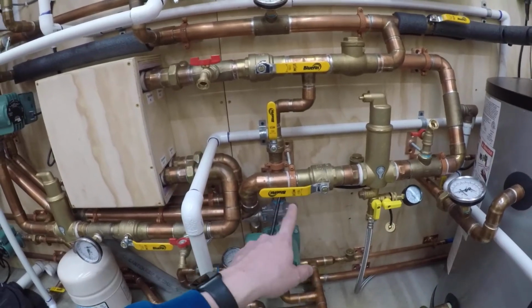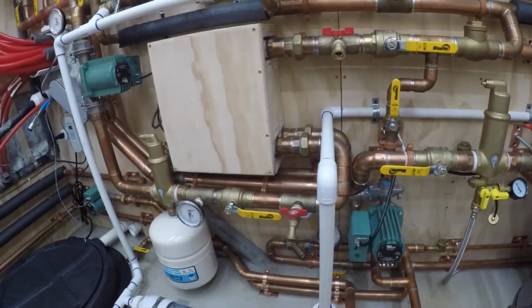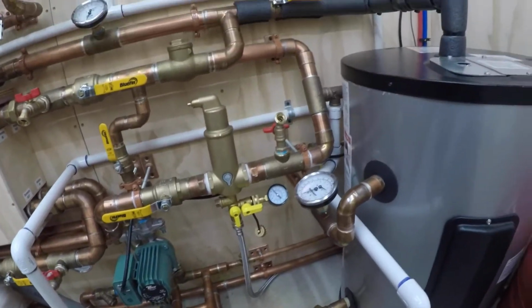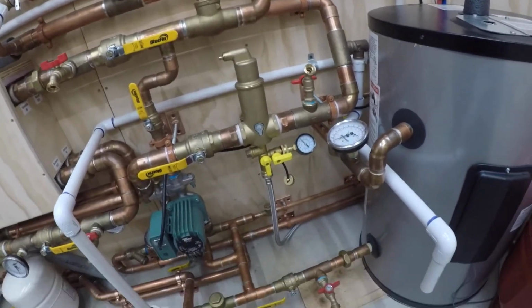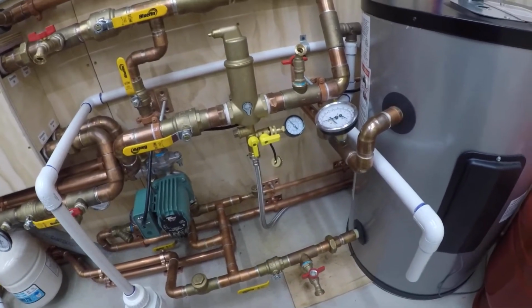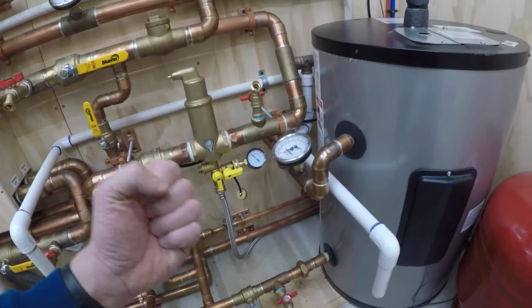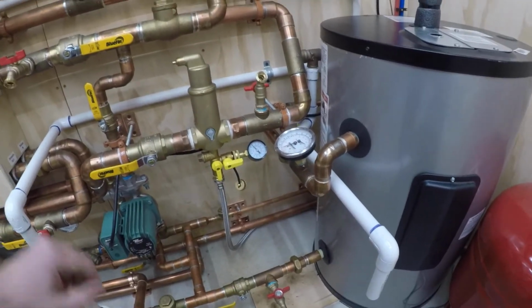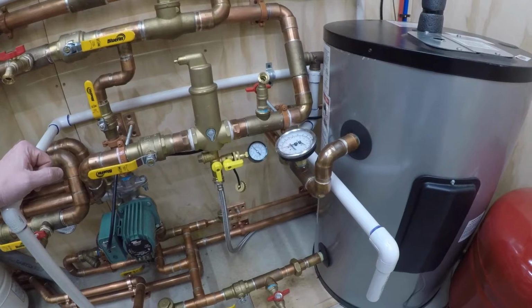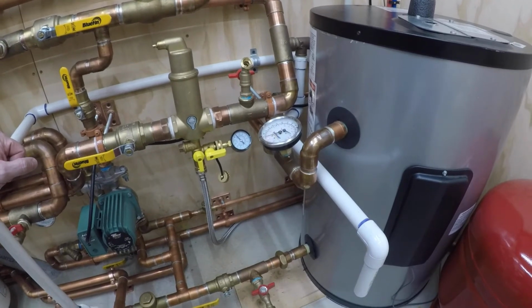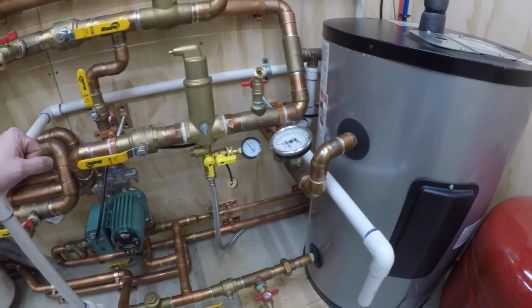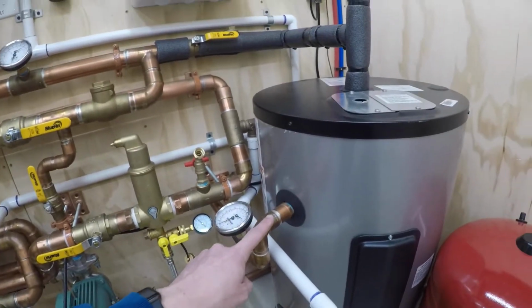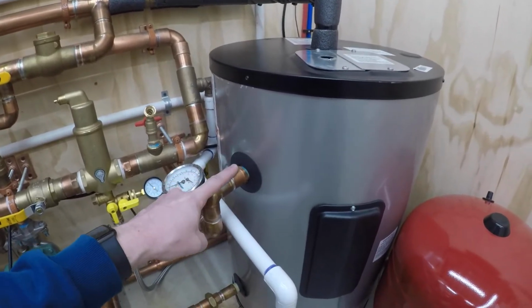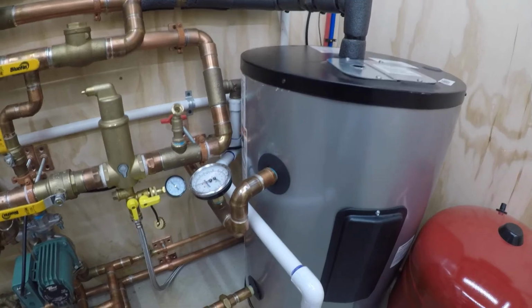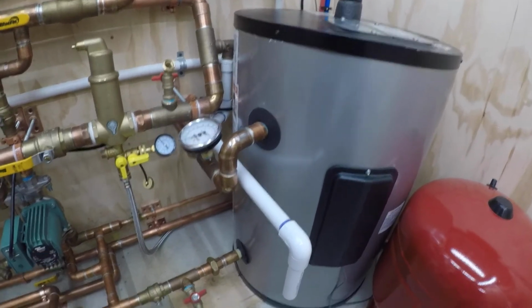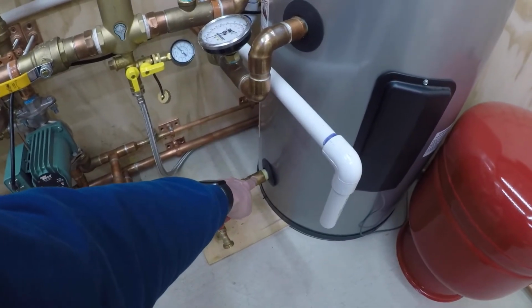It pulls the hot water through the three-way valve over, brings it back, puts it in here. Now, if it was doing that and say the shower was on, now you've got water leaving the system. So say you've got a shower head that's putting out 2.8 gallons a minute. At first, you'll have 2.8 gallons a minute of hot water leaving the tank here. You'll have 2.8 gallons a minute of cold water entering the tank here.